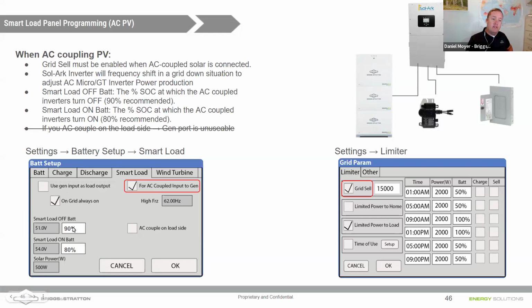So notice in the last one, right, we had it flip-flop. So now we're going to turn the smart load battery off when the batteries get to 90%. So we don't want the AC coupled solar producing when the batteries are getting full. But the smart load on is anything under 80%. So we want the AC coupled solar producing when the batteries are kind of low. Andrew, what do you think about those values? Do you think those are appropriate?